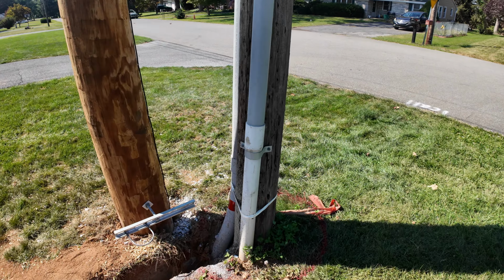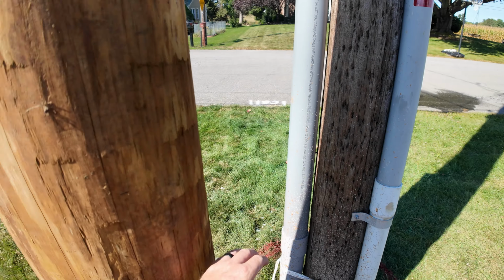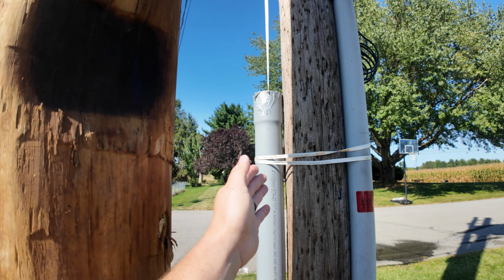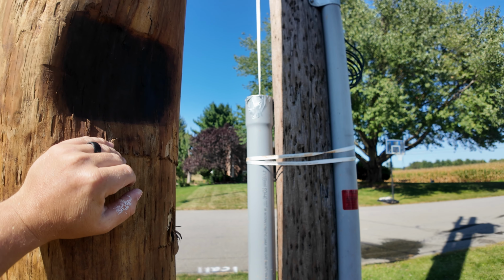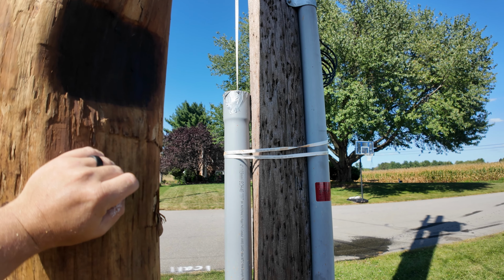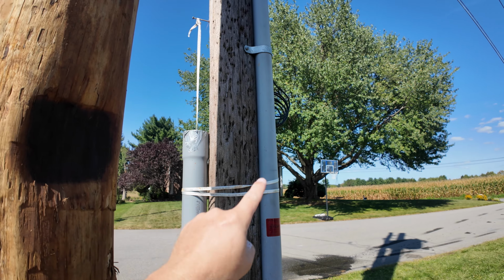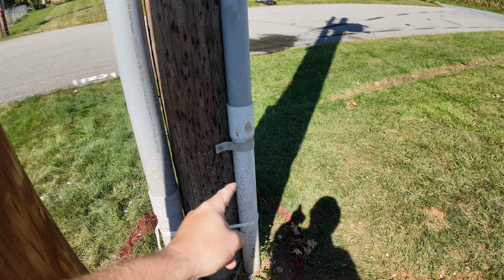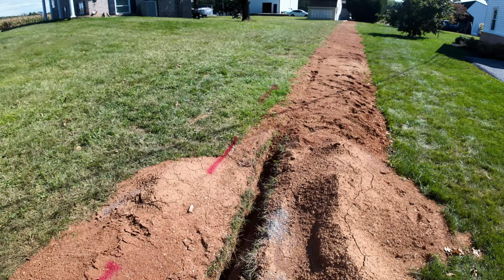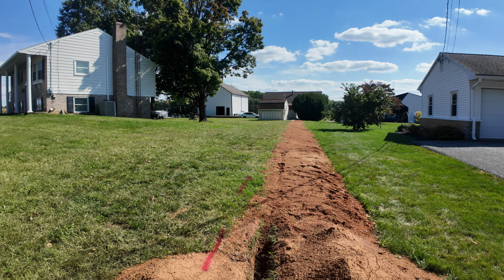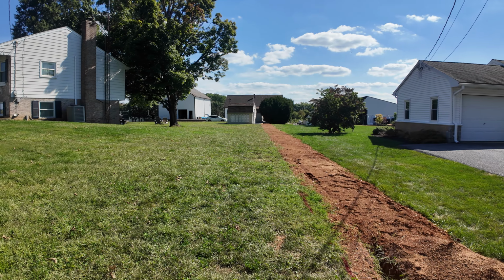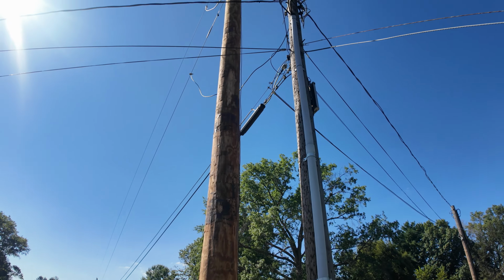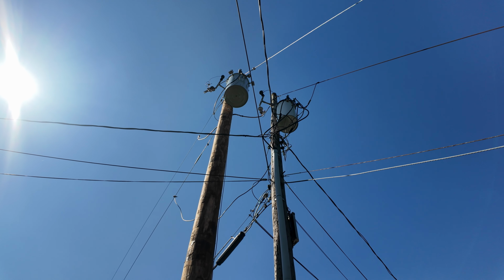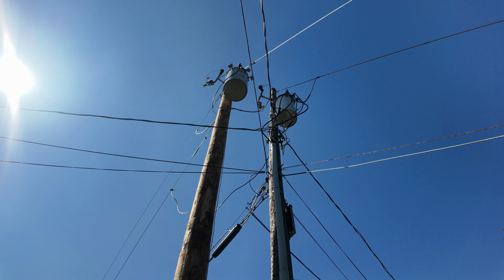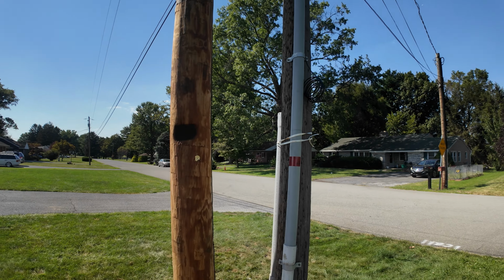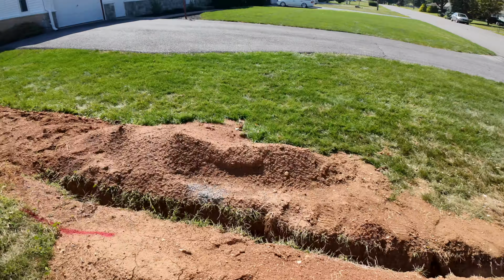So what's gonna happen? They redid a few things — they're coming out to run a 500 cable, meant to support a lot more, into our new conduit for the new shed. While they're here, they'll pull out the 350 and give me a brand new 500 cable all the way out to the shed. Between the properly rated cable and the brand new transformer, they said it'll run cool and we'll be able to use all the power we want, about 360 amps. It's been an interesting day for sure.